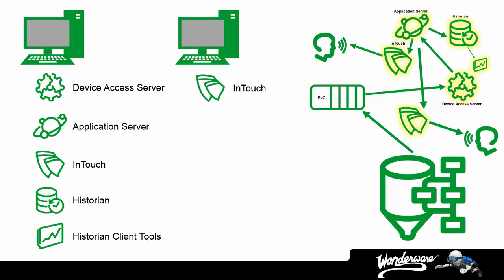Now, why don't we need all the other component licenses for the second node? Well, a single device access server could potentially provide all the connectivity or communications we need to all the controllers. Application server is simply handling the distribution of data, don't need another license for that, and the same historian will be used to store the historical records, so all we need is InTouch.